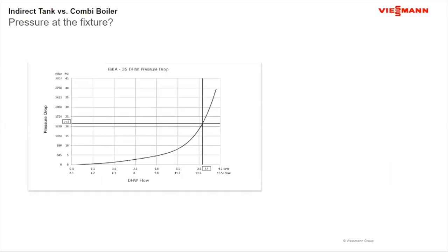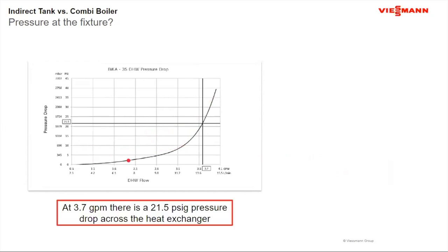Now, a final point I want to make is about delivery pressure. When I look at combi boilers, typically it's some sort of plate heat exchanger that I'm passing the water through. So you end up with a pressure drop curve of something like this on the domestic water side. When I look at flow rates, if I'm taking a single shower, I'm sitting somewhere about right here, probably around 1.8 to 2 gallons per minute. At that level, the pressure drop across the heat exchanger is about 3 psi, very minimal. So one person takes a shower, 3 psi, great water pressure in the house.